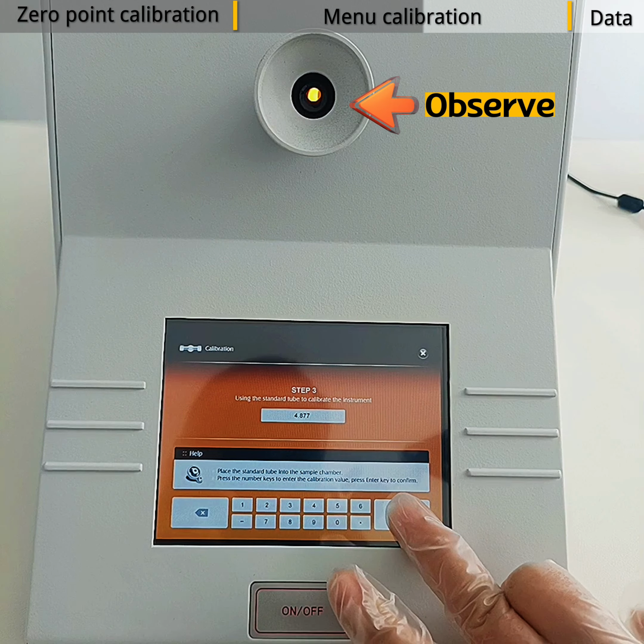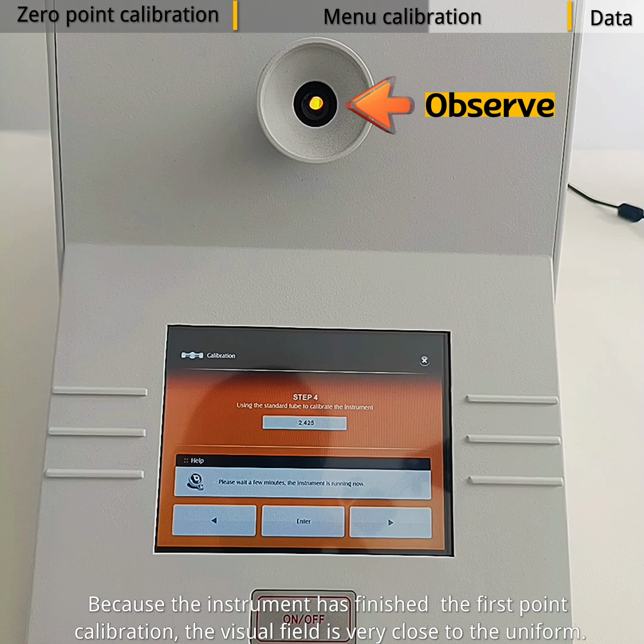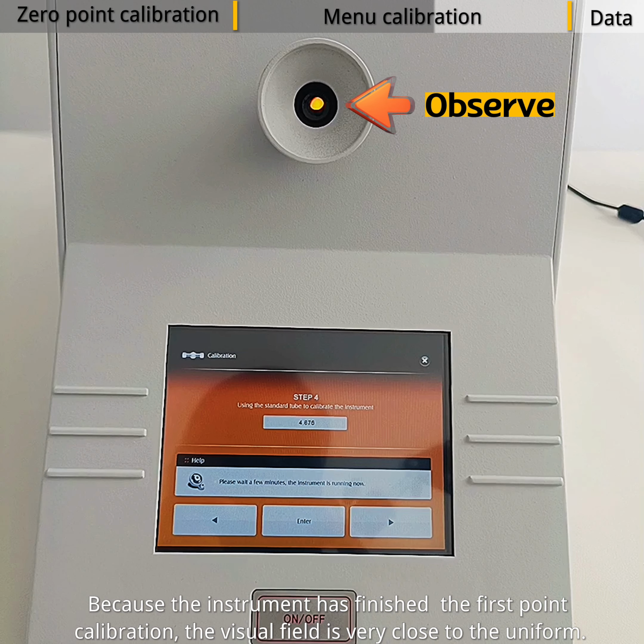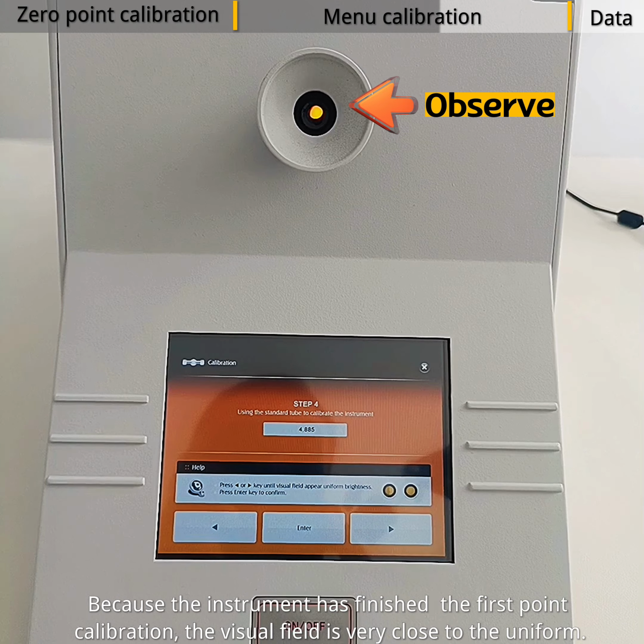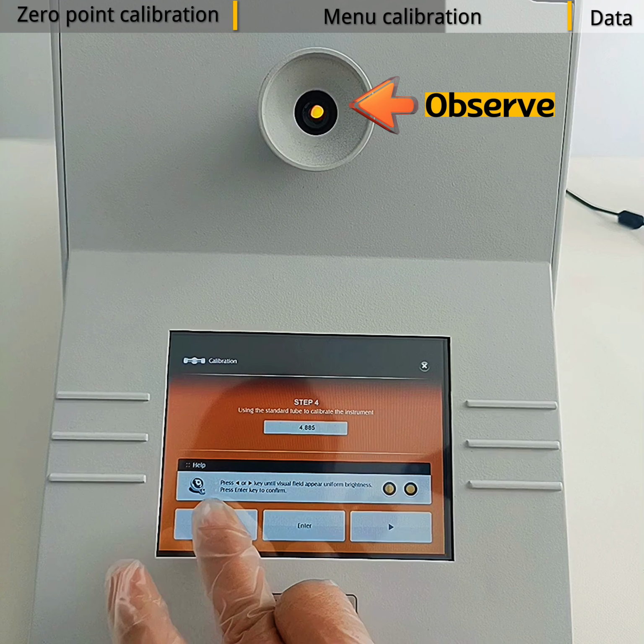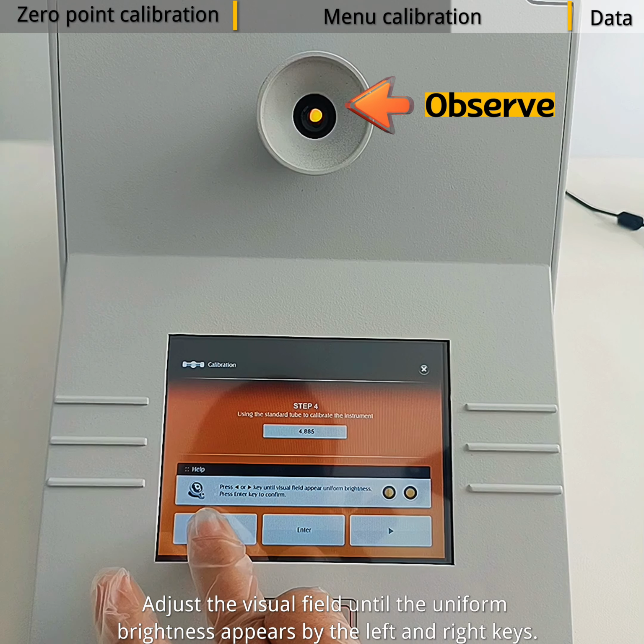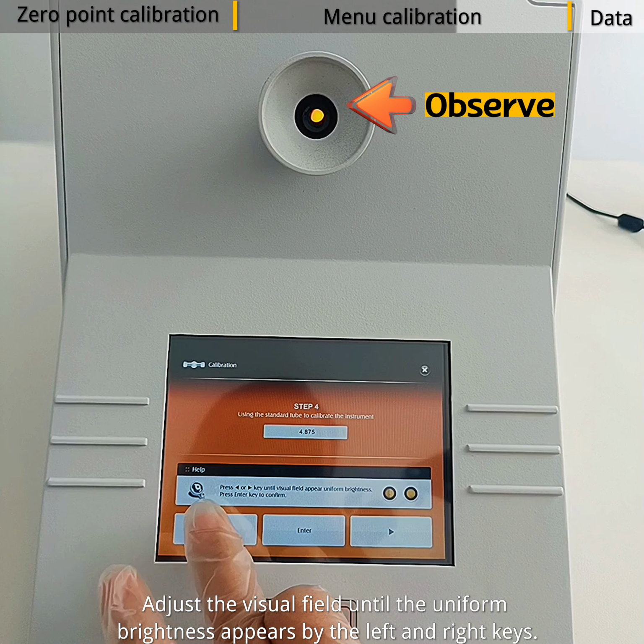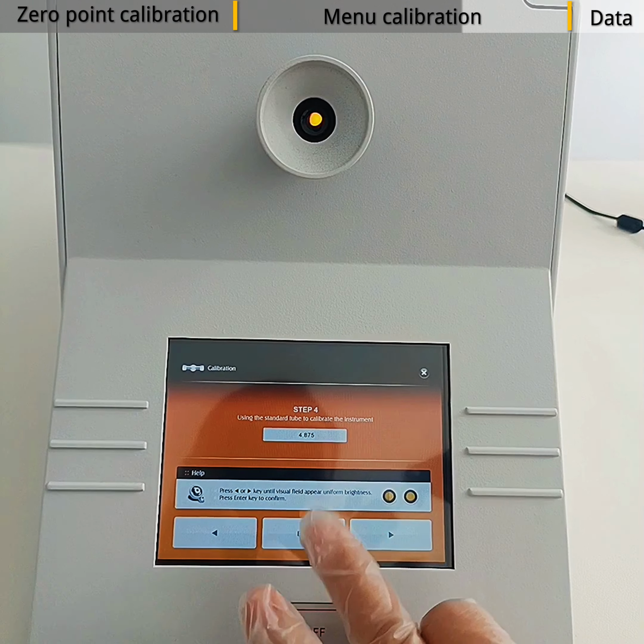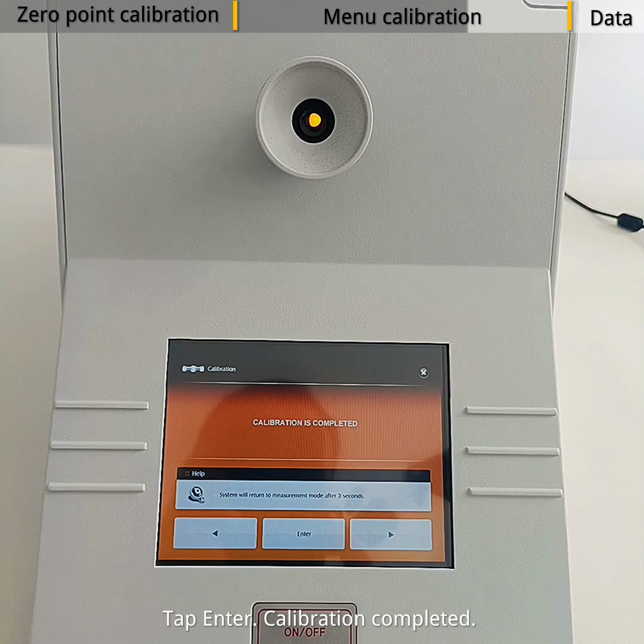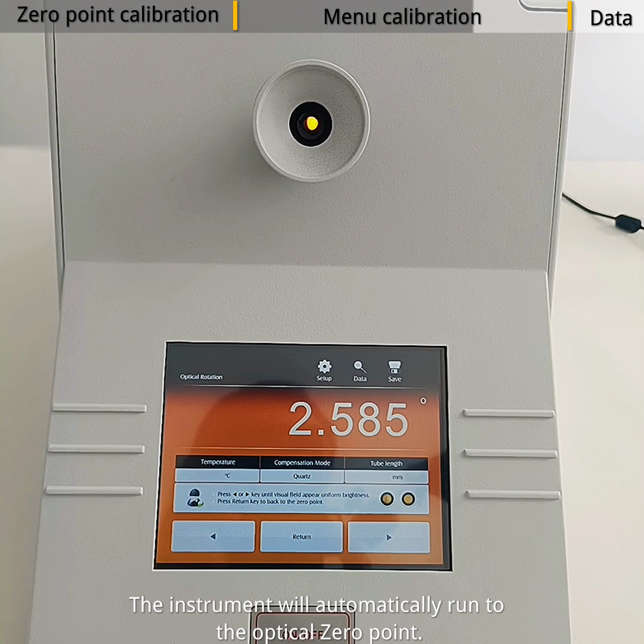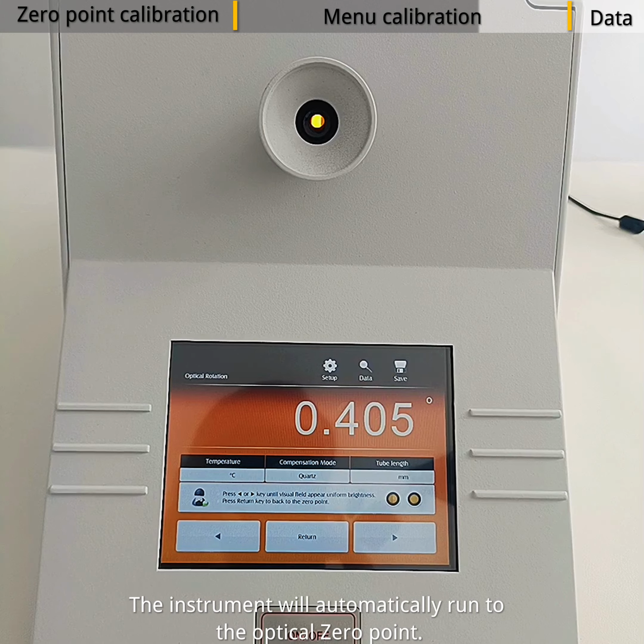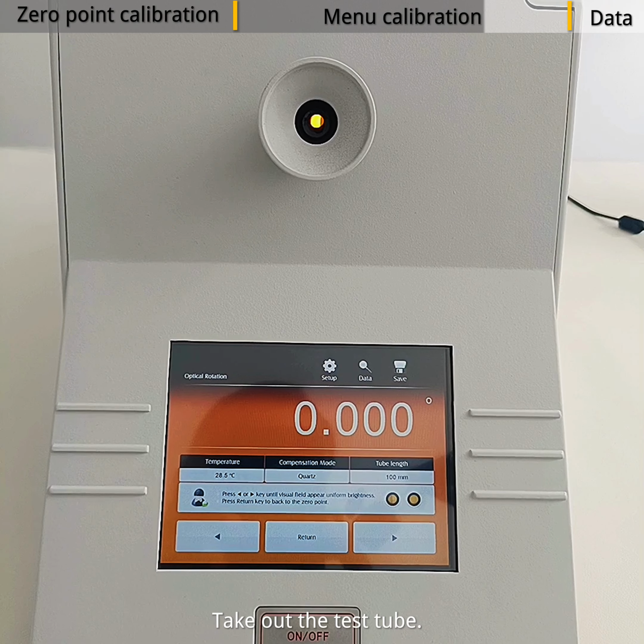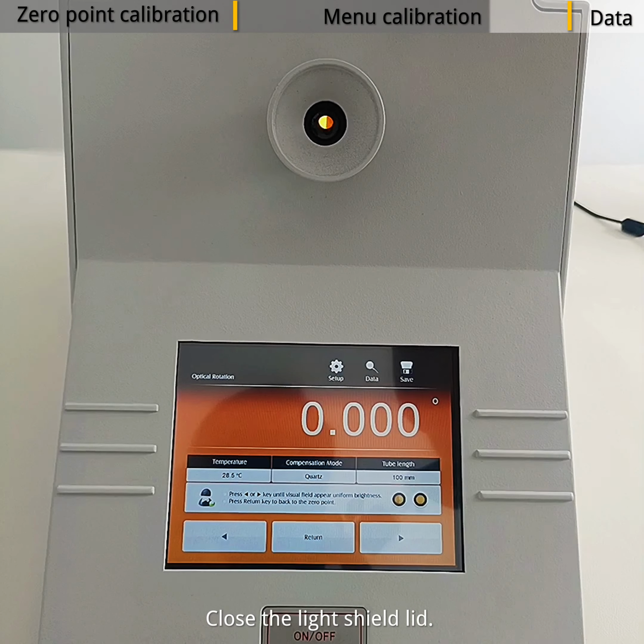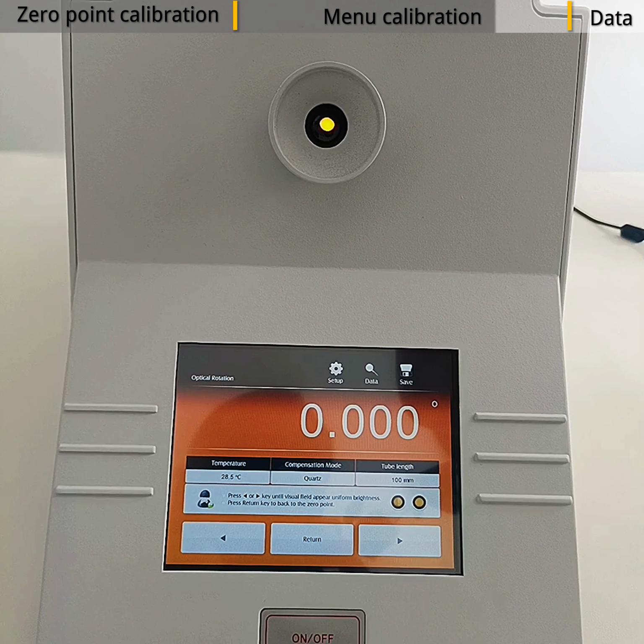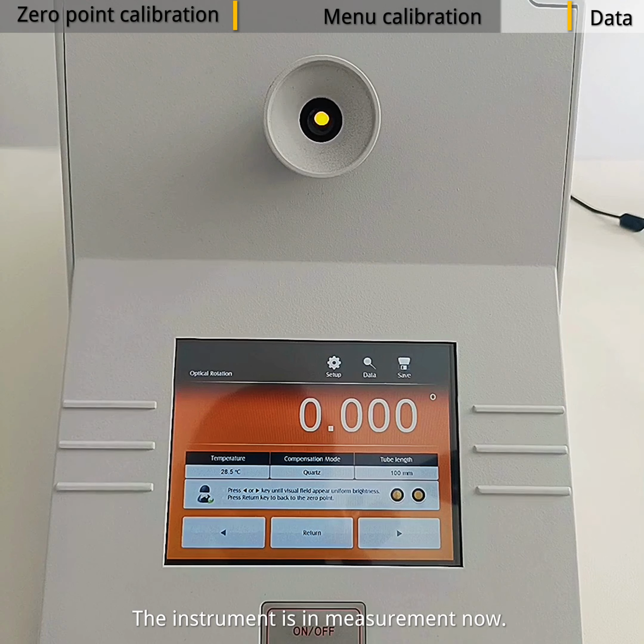Tap Enter. Because the instrument has finished the first point calibration, the visual field is very close to the uniform. Adjust the visual field until the uniform brightness appears by the left and right keys. Tap Enter, calibration completed. The instrument will automatically run to the optical 0-point. Take out the test tube. Close the light shield lid. The instrument is in measurement now.